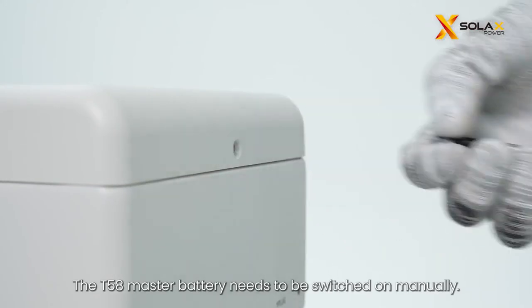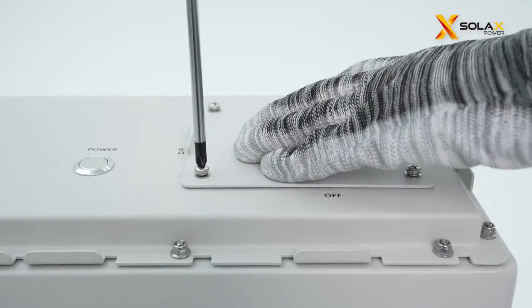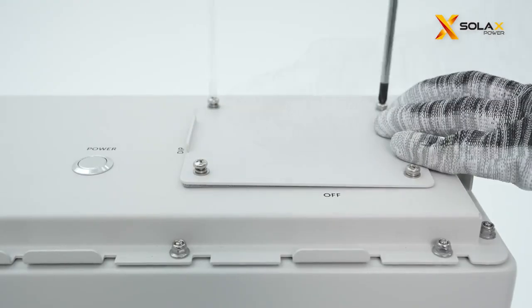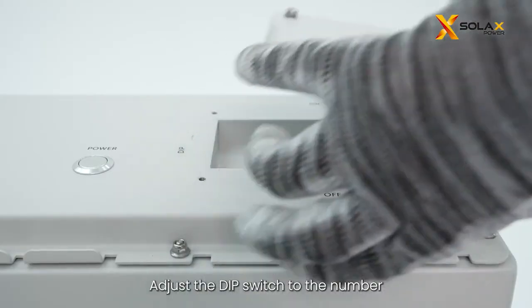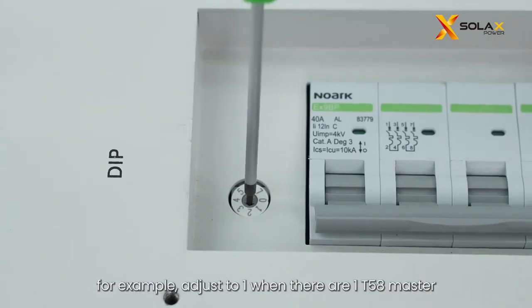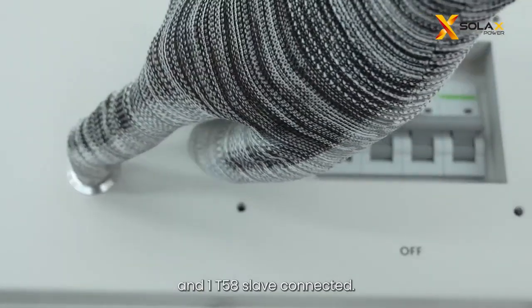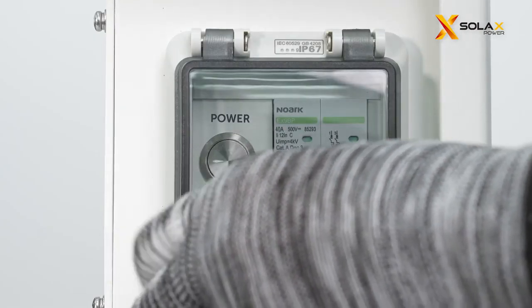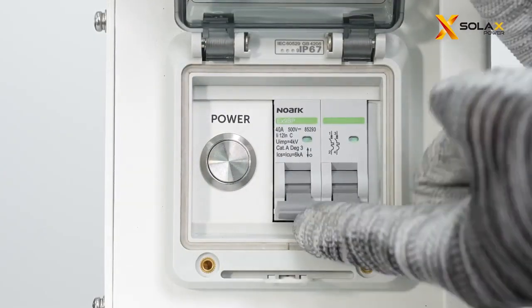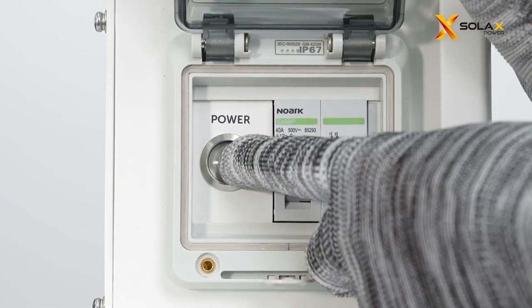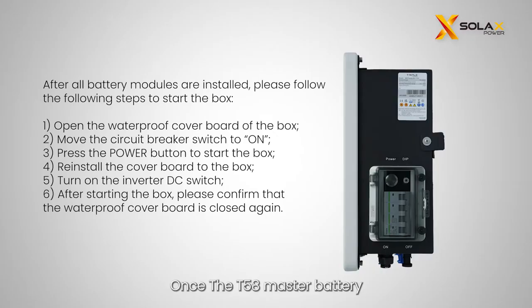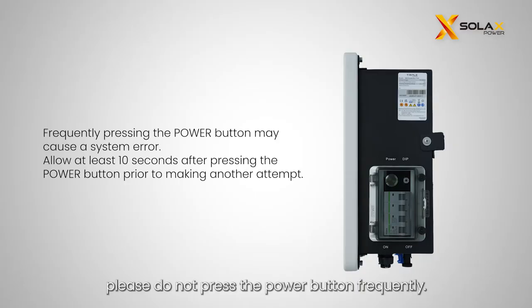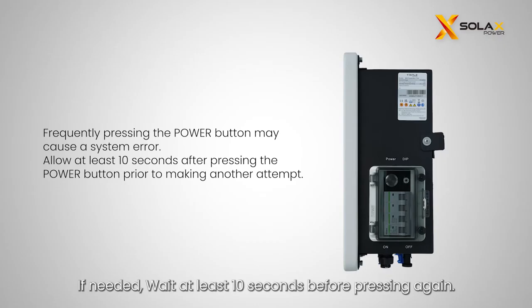The T58 master battery needs to be switched on manually. Adjust the dip switch to the number that equals to the T58 slave quantity. For example, adjust to 1 when there are 1 T58 master and 1 T58 slave connected. Press the power on button. Once the T58 master battery or the T30 BMS unit is powered on, next to turn on the box. Open the protective lid, turn the circuit breaker to on, then press the power button. To prevent system errors, please do not press the power button frequently. If needed, wait at least 10 seconds before pressing again.